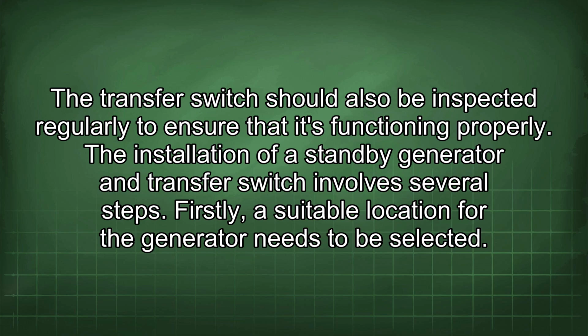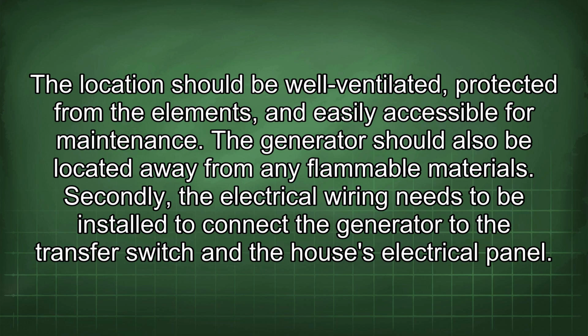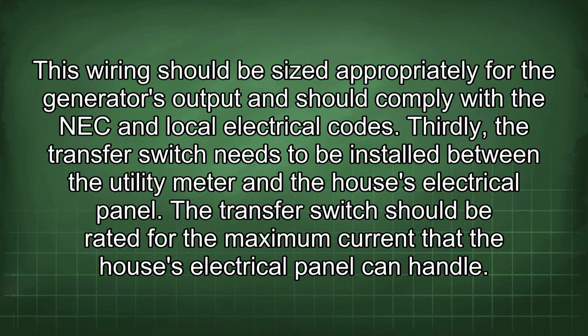The installation of a standby generator and transfer switch involves several steps. Firstly, a suitable location for the generator needs to be selected. The location should be well ventilated, protected from the elements, and easily accessible for maintenance. The generator should also be located away from any flammable materials. Secondly, the electrical wiring needs to be installed to connect the generator to the transfer switch and the house's electrical panel.